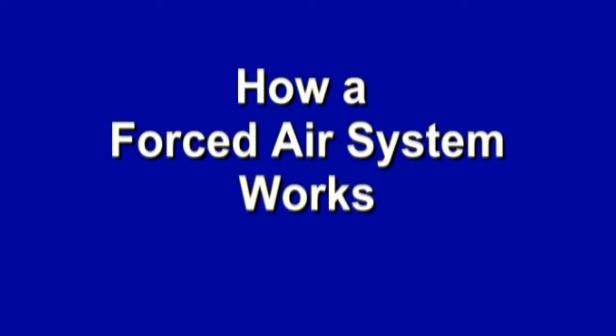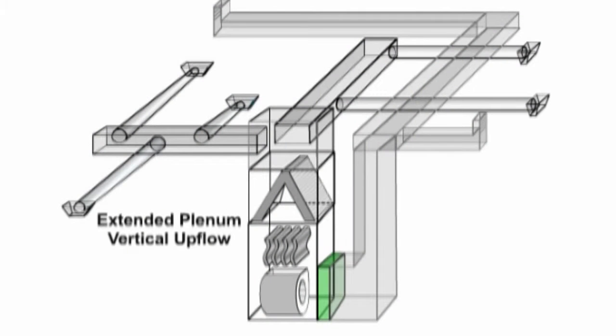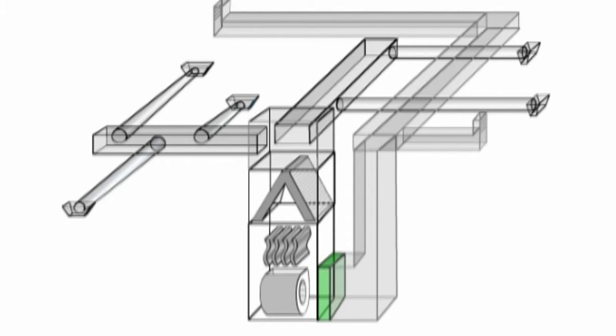How a forced air system works. What you're looking at is an extended plenum vertical upflow type of heating and air conditioning system. Let's add some names to the different parts and see how it operates. Let's start with the air filter. It's located on the outside of the main unit. To the left of that and inside the unit, you have a blower or fan that distributes air throughout the house and also pulls it back from the rooms.